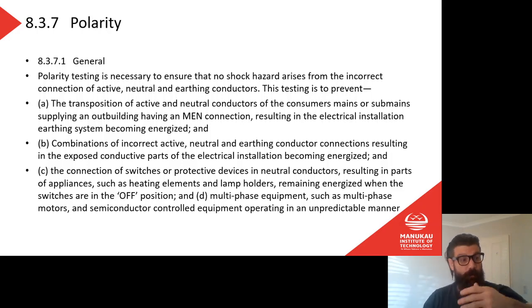So I need to test, for example, testing polarity would mean making sure that the phase terminal on a socket is connected to the phase wire and the neutral terminal is connected to the neutral wire. Polarity testing is necessary to ensure that no shock hazard arises from the incorrect connection of active, neutral and earthing conductors. So if I switch them around accidentally somewhere along the way. This testing is to prevent the transposition, so switching, of active and neutral conductors of the consumer mains or submains supplying an outbuilding having an MEN connection, resulting in the electrical installation earthing system becoming energized.